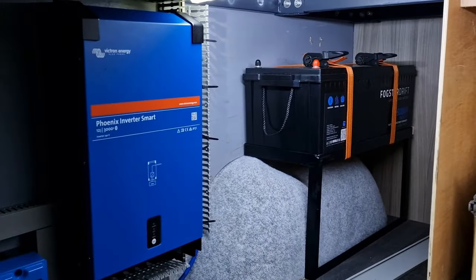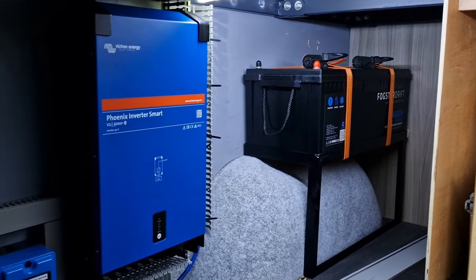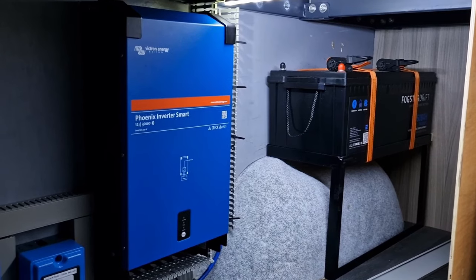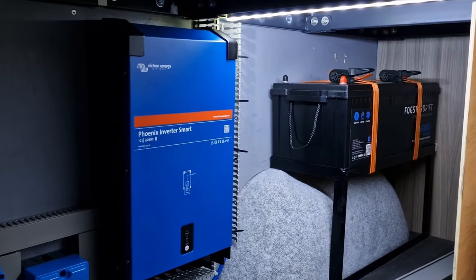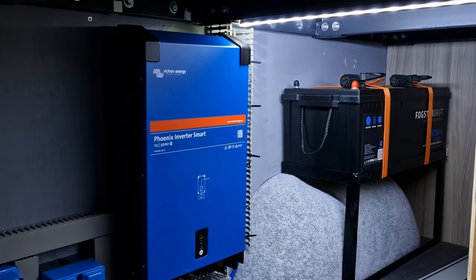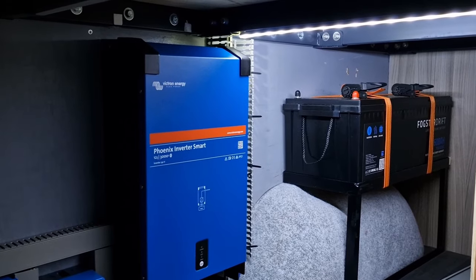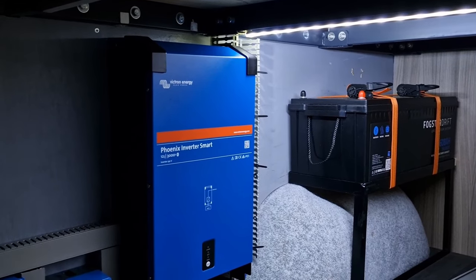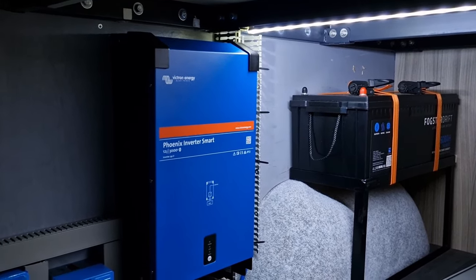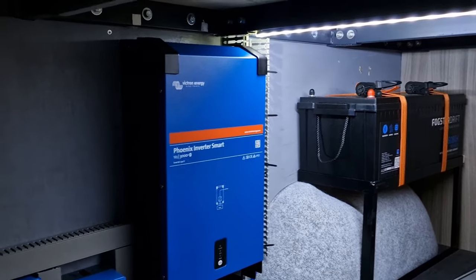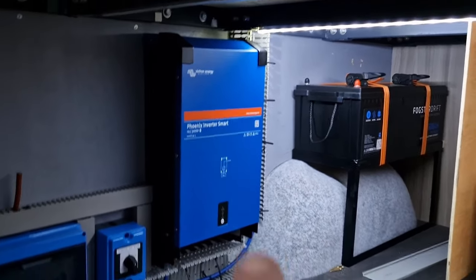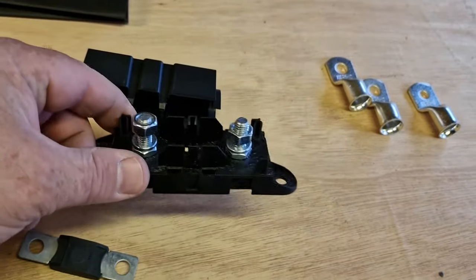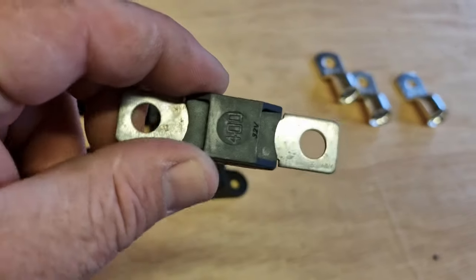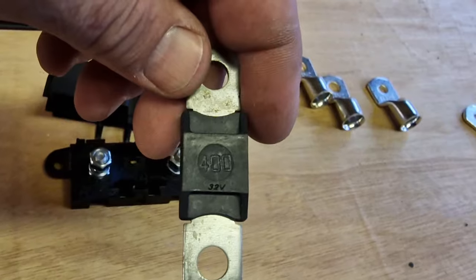The BMS on that battery is 250 amps. The recommended size of fusing for the cable, and the cable size from Victron, is 95 mil, with a 400 amp fuse. So that's what we're going to install, because I don't want to void any warranty on that. We're going to use a mega fuse. This is a 400 amp one, hopefully you can see it there.